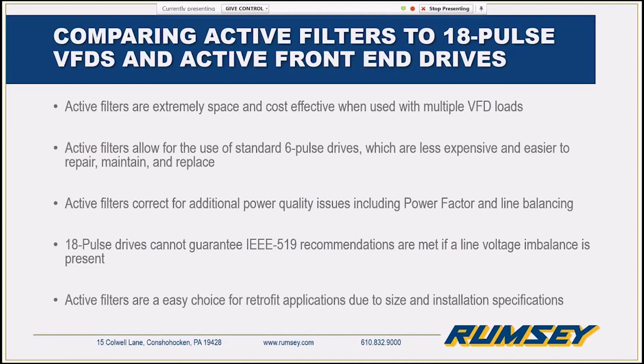What does that do for you when you get to use the active filter instead of one of these other drives is that you get to use those 6 pulse drives, which Rumsey has readily available on the shelf for you. If you have a problem, there'll be one with you again the next day. Meanwhile, the lead time for those other pieces of equipment is much longer, just like an active harmonic filter, except when the active filter goes down, as we said, the process doesn't stop. While if one of these goes down, your process would stop until you got a new drive.